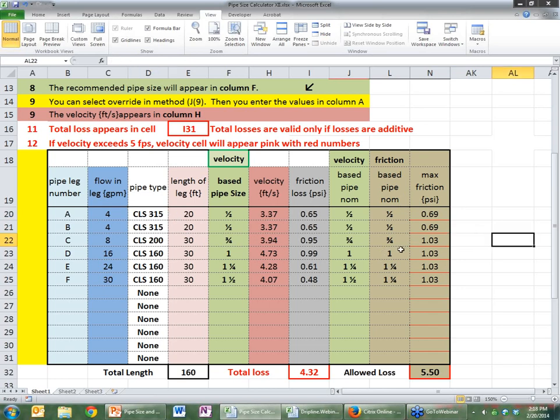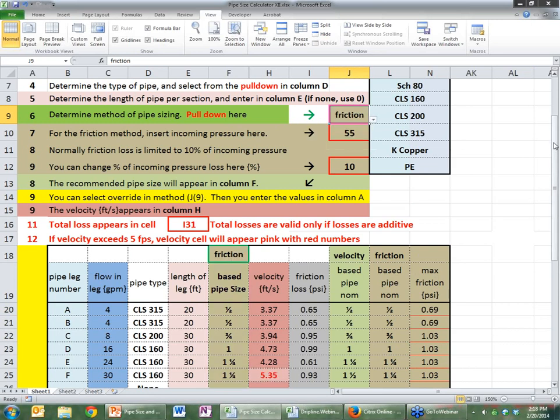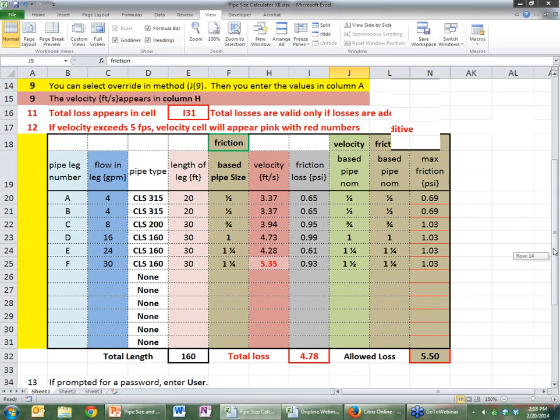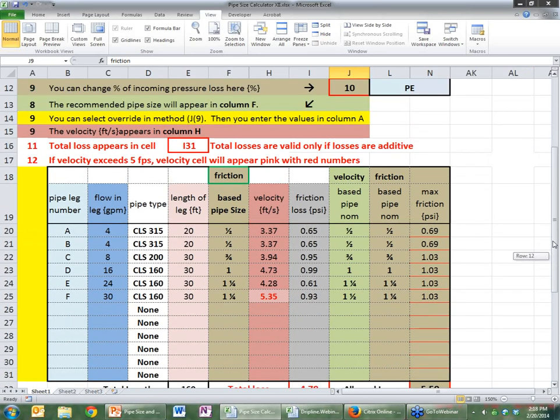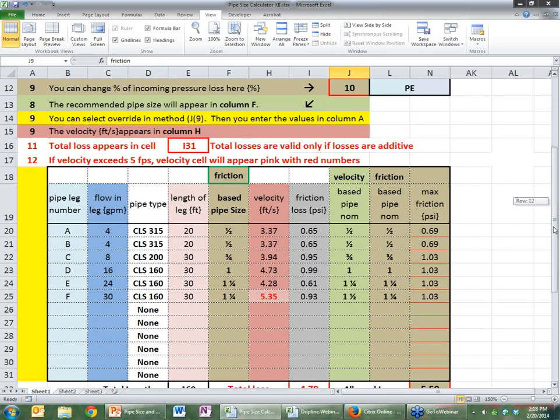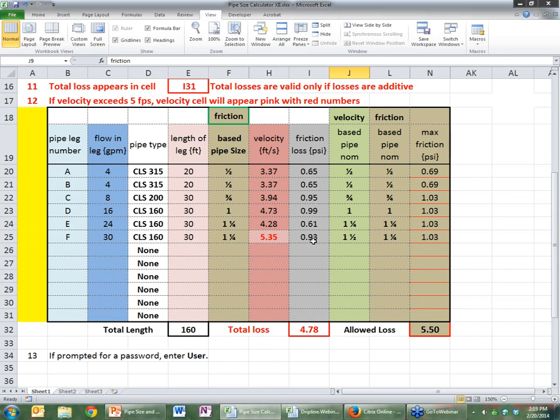Now, let's look at the summary of the table. Let's go back to friction for a minute. Now, in the friction method, if we can lose 10% of our incoming pressure, we can lose 5 and a half pounds. So the allowable loss is here 5 and a half. That 5 and a half is allocated amongst these pipe sections by the relative lengths. So there's 160 feet. So 30 of 160 of this 5 and a half can go here, which is 1.03 pounds. So that's the limit, and that's what we use to pick the pipe size with. And when we do it on friction, we're not looking at velocity. We're simply looking at friction. So we will use a total of 4.78 PSI of our allowed 5.5.